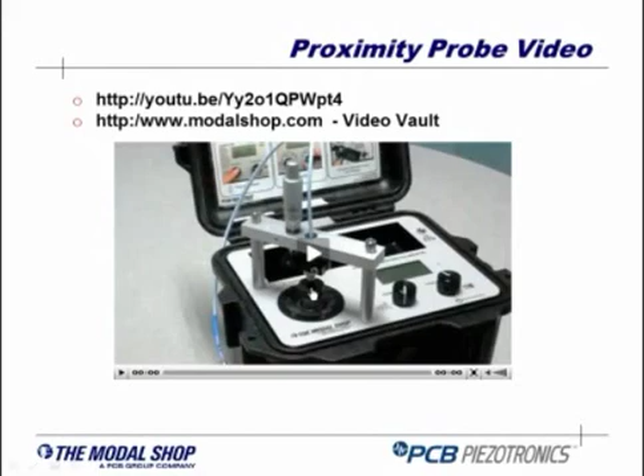Here you see the prox probe going through the apparatus, close to the gap and close to the target. This is the type of measurement our customers are interested in. You start with the prox probe very close to the target - typically a quarter of a millimeter away, or 10 mils - and you move the prox probe away from the target, and given how they're powered up, you get a negative voltage out.